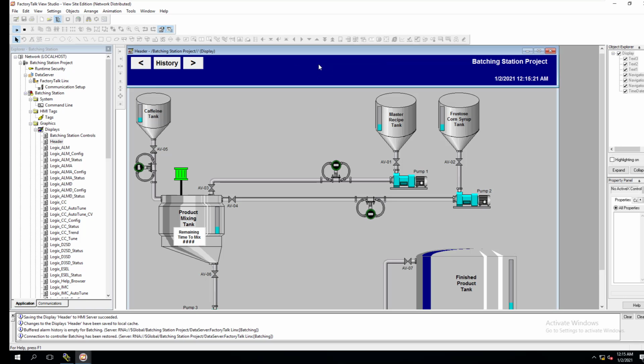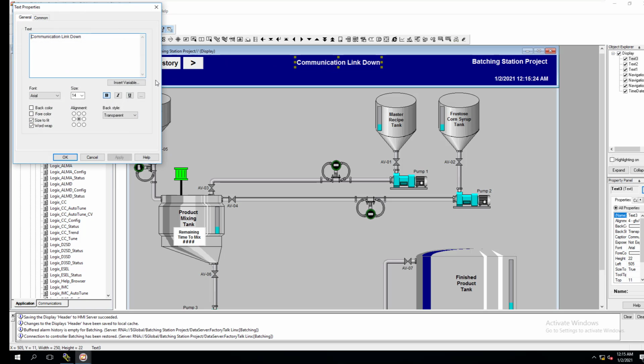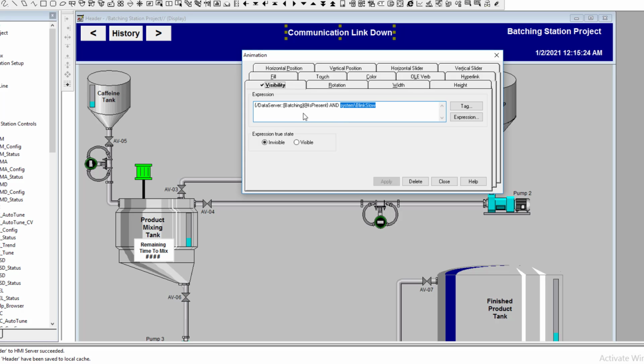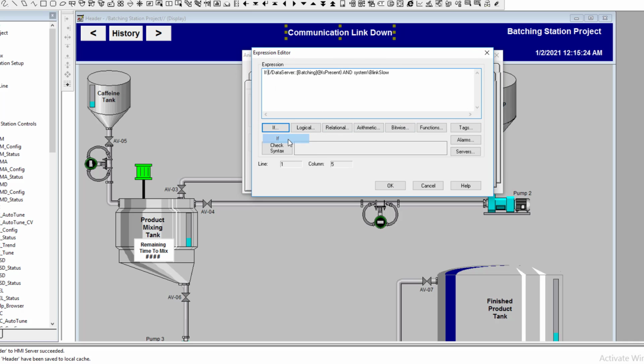So this right here is actually indicating, oh, I know why that's happening. So we want to do this. We want to say and it is blinking. Actually we need to change this syntax. We need to change this to an expression, and then an expression to say if this is present, and if the blink status is on, and then one, else zero. Okay, so this is basically enabling. All we're saying is, if you think about this as a rung of ladder logic, one would have to be on.